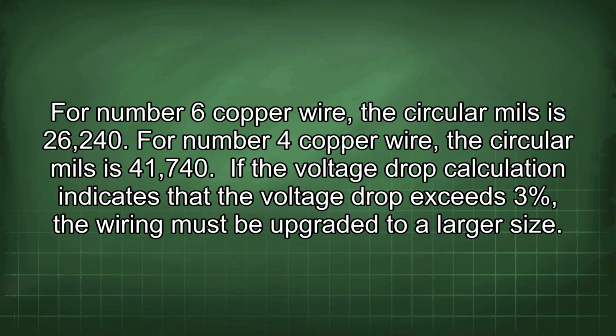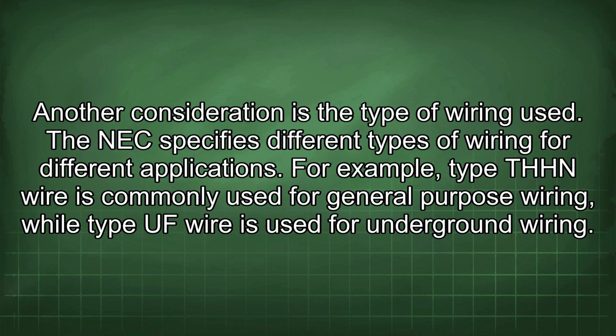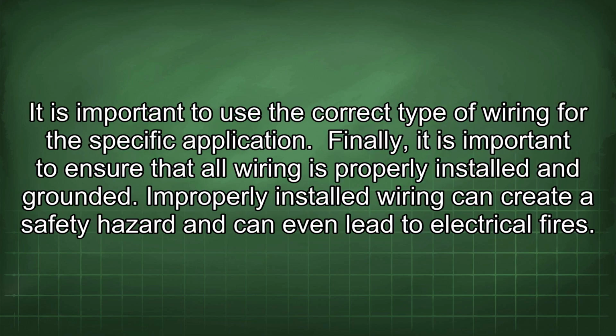If the voltage drop calculation indicates that the voltage drop exceeds 3%, the wiring must be upgraded to a larger size. Another consideration is the type of wiring used. The NEC specifies different types of wiring for different applications. For example, type THHN wire is commonly used for general purpose wiring, while type UF wire is used for underground wiring. It is important to use the correct type of wiring for the specific application.